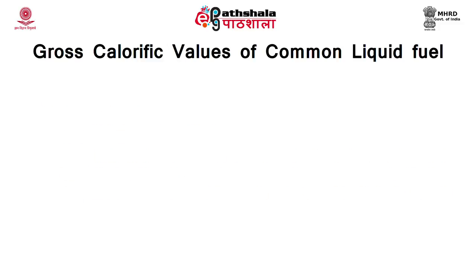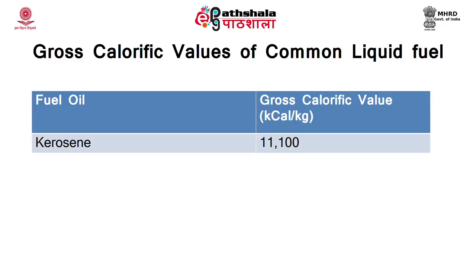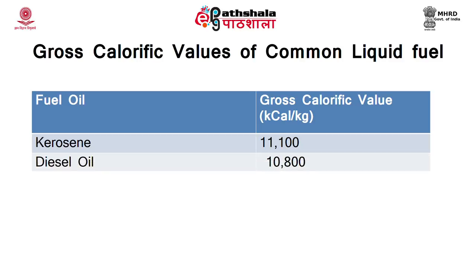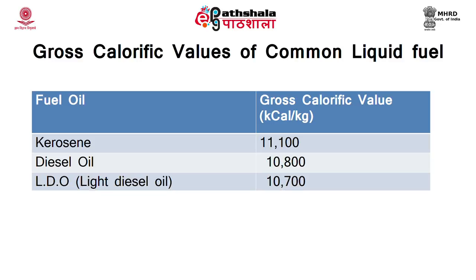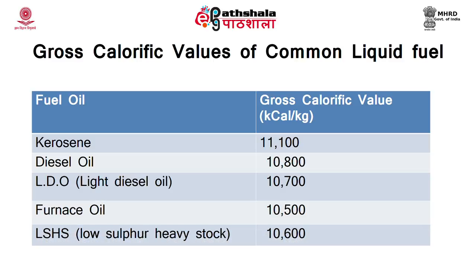This table shows the gross calorific value of common liquid fuels. Kerosene: 11,100 kcal/kg; diesel oil: 10,800 kcal/kg; light diesel oil: 10,700 kcal/kg; furnace oil: 10,500; low sulfur heavy stock oil: 10,600. These are the gross calorific values.